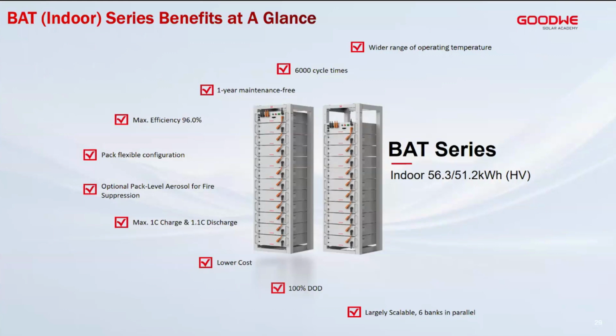Now, what are the unique features you'll be getting once you have this product installed? The operating voltages and operating temperatures are very broad or wide. This is just to assure you that the African market, however hot it goes, will be covered. To get the actual specific working range, we'll also be sharing the data sheet of this battery itself. The battery is able to reach over 6,000 cycles. This is guaranteed. It comes with 1-year maintenance free, so you can store the battery in your warehouse for up to a year without doing any maintenance, that is charging and discharging to protect the health of the batteries. The round trip efficiency is up to 96%, so you'll be using up most, if not all, of the power that's stored in this battery.